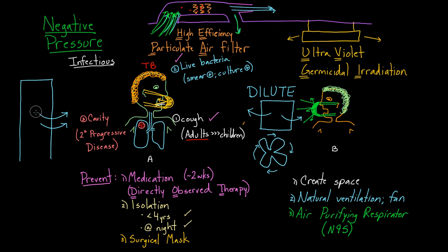Especially if you do it right, if you close off all these doors and you close these windows, then you definitely create a negative pressure. And what that means is that now you can really protect the area around because you close off the door, you close off the window, and now there's no way that a TB particle can leave and go into the hallway. If there's a little bit of a gap underneath this door, if that's the only crack in this room, then the negative pressure is going to make air flow through that crack into the room instead of air flowing out into the hallway.